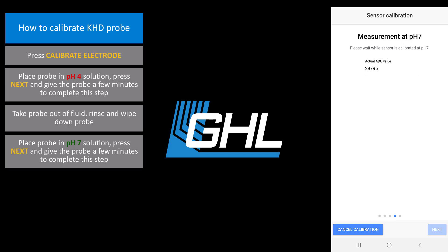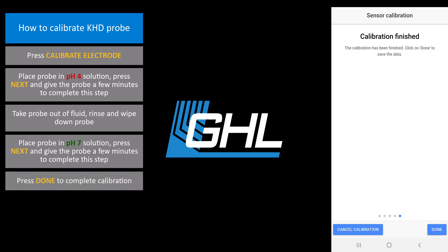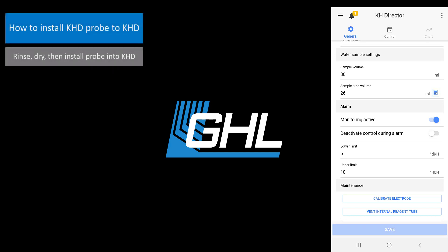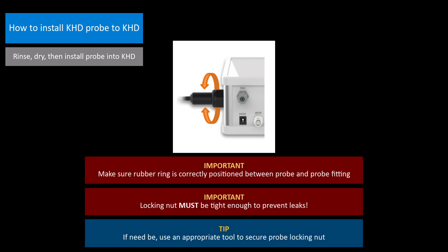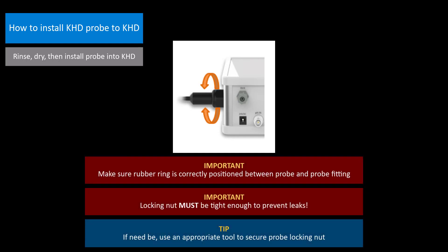When you get to this screen, the calibration will be complete. Take the probe out of the fluid, rinse, dry, then insert the probe into the KHD probe port. When installing the probe, make sure the rubber ring from the locking nut is correctly positioned. Also make sure the locking nut is tight enough so you don't have any leaks from the probe port. If need be, use an appropriate tool to carefully tighten the screw connection.